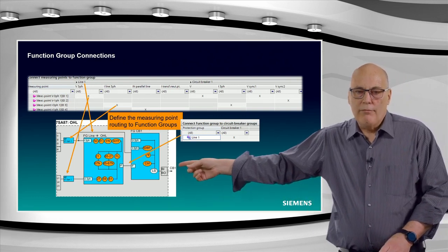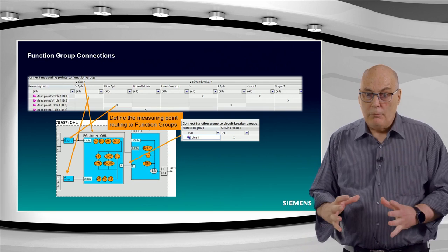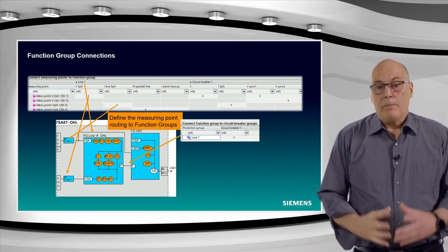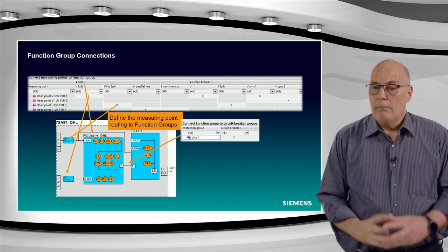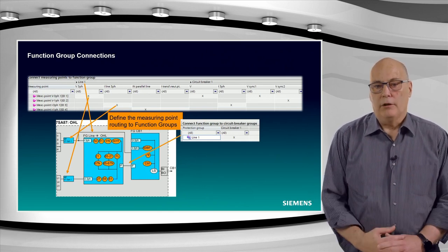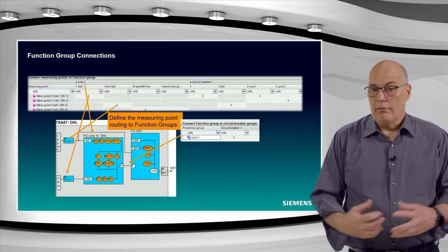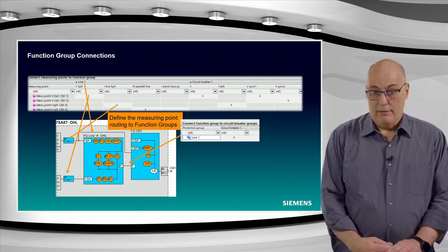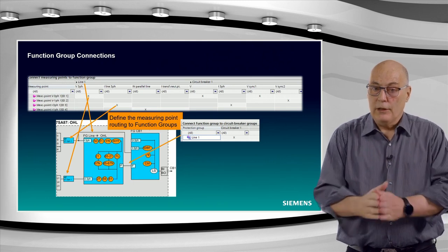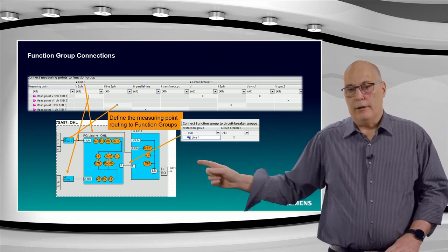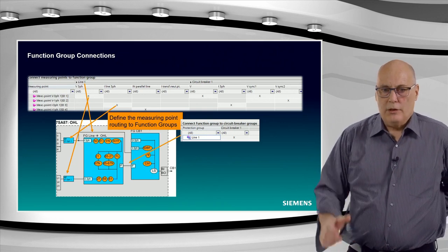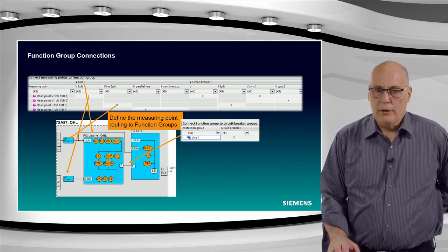Here you derive this via a function group circuit breaker, because all the logical devices like auto reclosure, we'll see later on, those are not implemented inside a line, those are implemented in the circuit breaker where they belong, like a sync check function, auto reclose, breaker failure, and so on, are done inside a function group circuit breaker. And the trip command of the line goes to this logical circuit breaker, and the circuit breaker then processes that onto the outside. This is the structure of SIPROTEC 5.